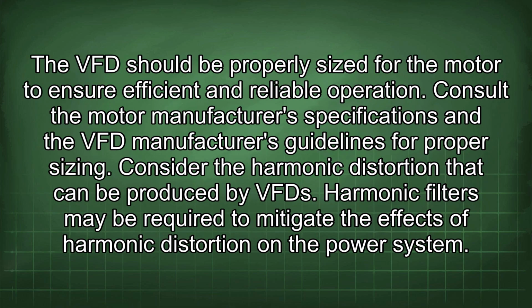The VFD should be properly sized for the motor to ensure efficient and reliable operation. Consult the motor manufacturer's specifications and the VFD manufacturer's guidelines for proper sizing. Consider the harmonic distortion that can be produced by the VFD.